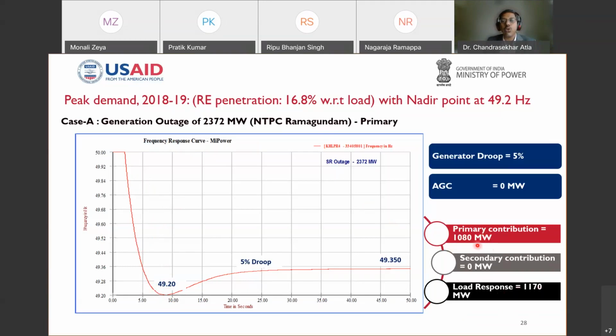It is not only the primary response from the generation, load also contributes, as mentioned by Dr. Nagaraj sir. So 1170 megawatt load response. With that, the frequency is arrested at 49.2. While arresting the frequency at 49.2, two critical roles happened: one is the inertial response, and by the time partial primary reserves also started participating along with load response. Over time, the full primary reserves are deployed, and around 25 seconds, complete primary reserves are deployed into the system, and frequency has settled at 49.3.